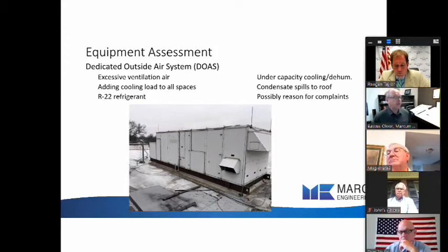Other things I noted is the condensate spills right on the roof and runs across the roof. That's degrading our roof. We don't need that. We need to pipe that directly to a roof drain. It's using the older non-environmental friendly R22 refrigerant that is very hard to get now. It costs a lot per pound to buy that and to keep the refrigeration system charged. And as I said, this is the chief culprit of complaints of comfort, I believe.